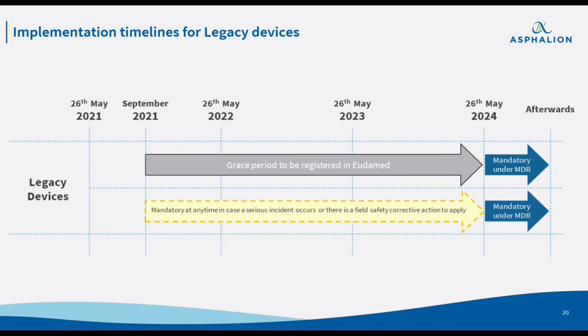This way, you will ensure that in the event of an incident, your products are already ready or even registered within the EUDAMED database, and any vigilance issues can be reported without problem. At the same time, once your MDD or IVDD certificates expire, you will already have all the information regarding your devices in EUDAMED, and you will just have to link your new MDR or IVDR device with the previous legacy device. We will come back to this point of linking legacy devices with MDR or IVDR devices at the end of the presentation.